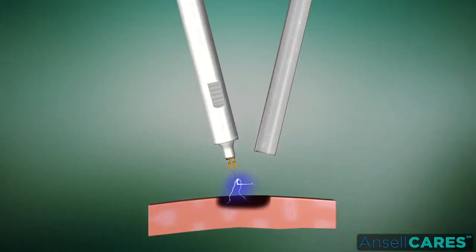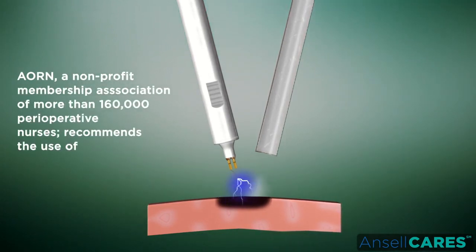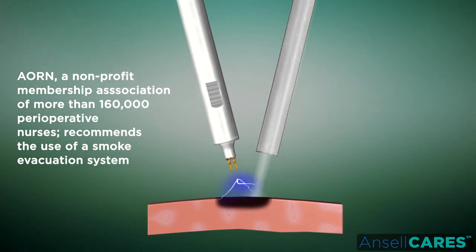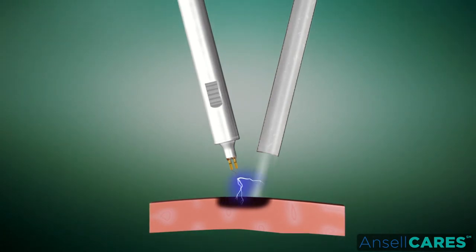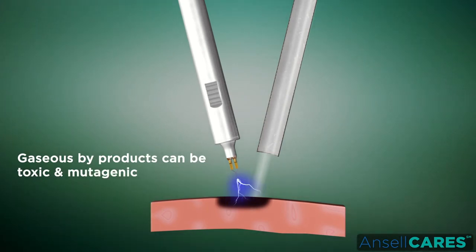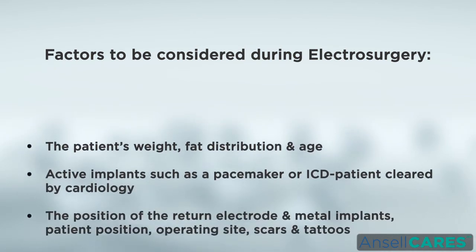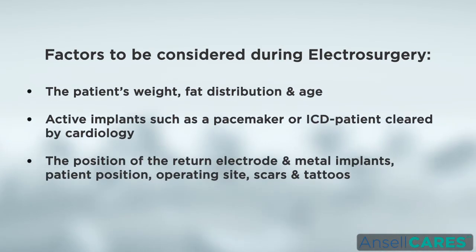AORN — a non-profit membership association of more than 160,000 perioperative nurses — recommends the use of a smoke evacuation system to protect perioperative personnel from inhaling smoke generated during electrosurgery. AORN cites the potential for bacterial and viral contamination of the smoke and warns that gaseous byproducts can be toxic and mutagenic. According to AORN, the following patient factors should be considered during electrosurgery: the patient's weight, fat distribution, and age; active implants such as a pacemaker or ICD with patient clearance by cardiology; the position of the return electrode; metal implants; patient position; operating site; and scars and tattoos.